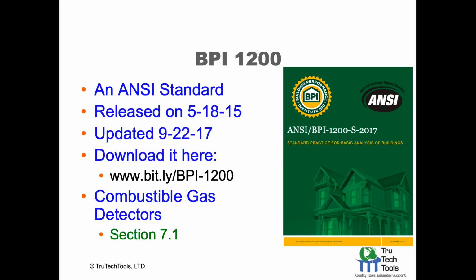The combustible gas detectors are in section 7.1. We're going to examine 7.1 now, now that we gave you an illustration of how the product works, what it's made of, and why it was designed. We're going to talk about its application or use. So I call this test instrument survivor. This is to show you how BPI ended up specifying pretty much exclusively the Sensit HXG-2D. It wasn't that they picked a manufacturer, it was the specifications that led you there. So I'm going to go through the three or four essential elements of the standard which ended up making the Sensit HXG-2D the winner here, the survivor.